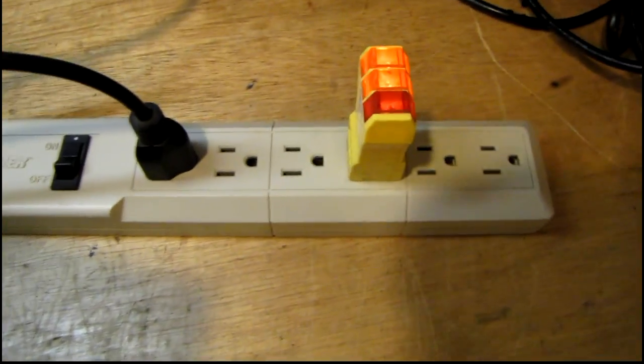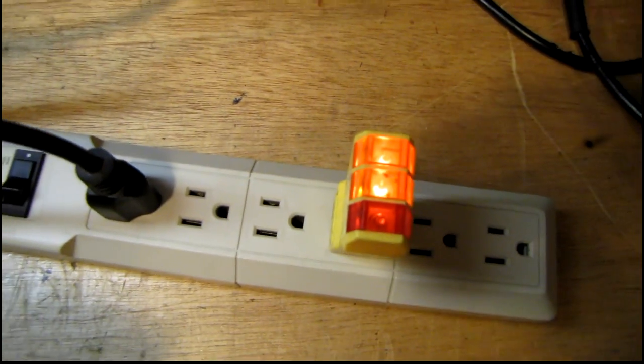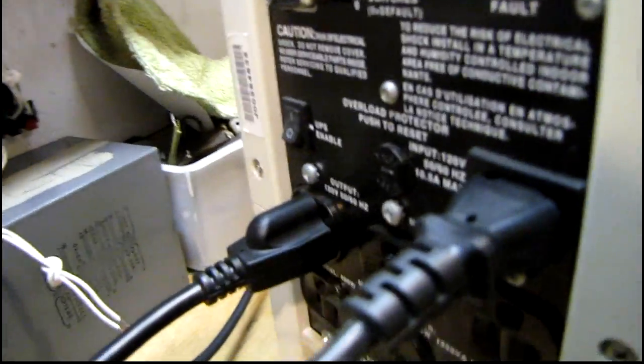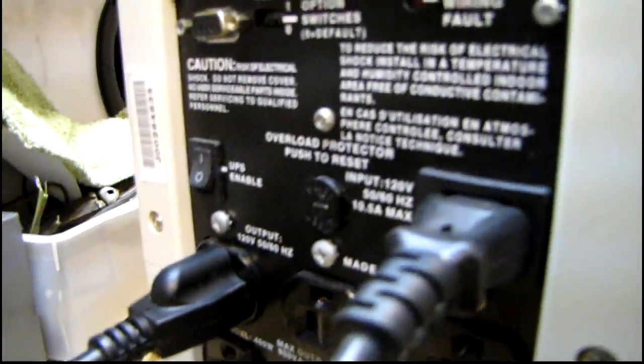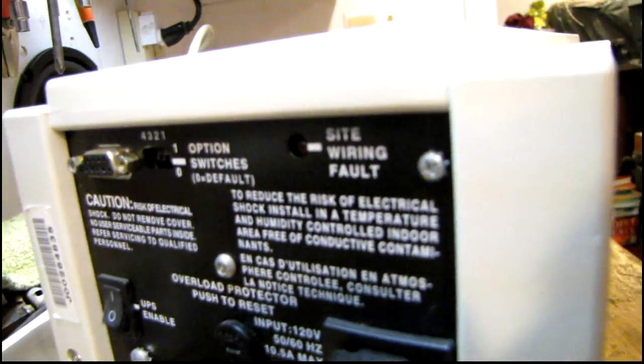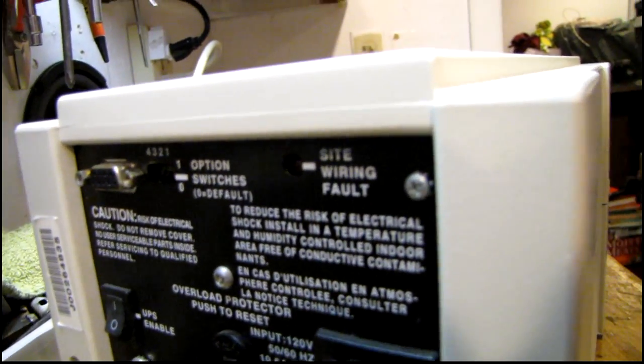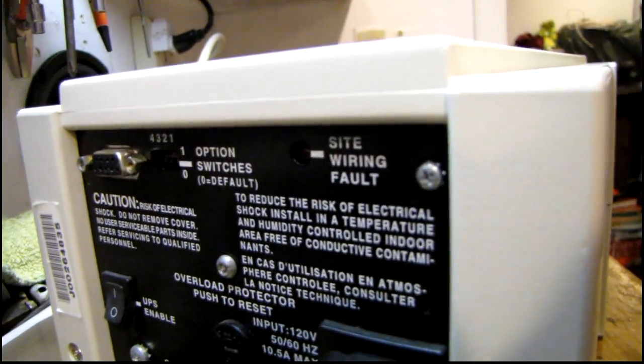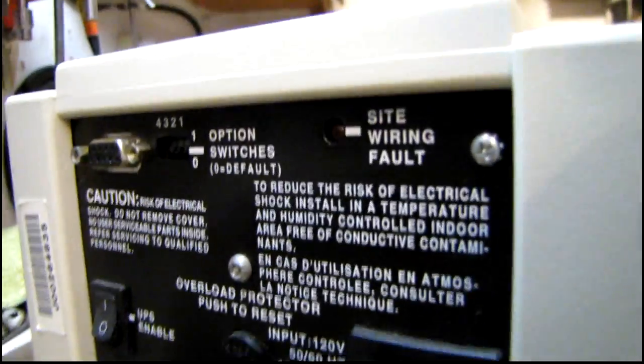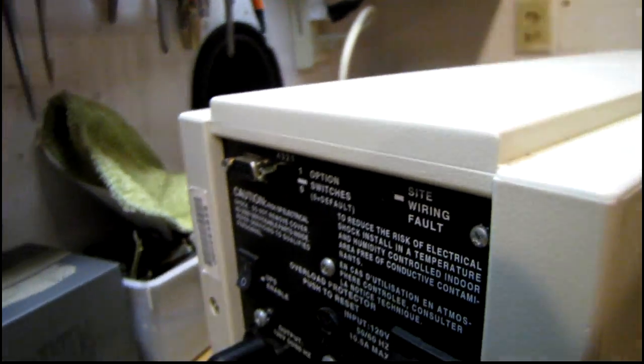Make sure the ground is good by using a plug tester. And also, on the back of the UPS, there's a small light that says site wiring fault. That will light up if the ground is bad. So just make sure that your earth ground is good. And then you can go ahead with this.